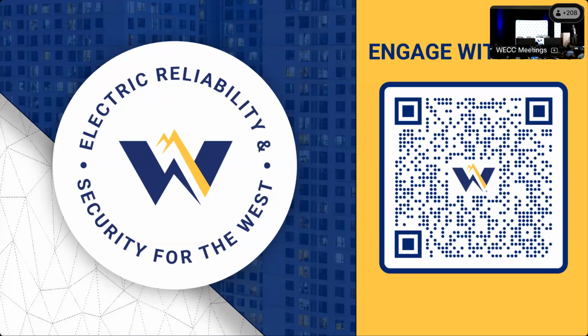It's kind of interesting. In the West, we maintain time error control. I don't know if anybody realizes that, but we do keep track of the frequency deviation over time. We call that time error. And we generally swing about plus or minus 200 seconds of time control in the West. Why that's important is clocks used to run on it. And if you've got a microwave and it's never in time, it's because we're swinging our system frequency that much on a yearly basis. So you can set your microwave today, and in 2 months it's going to be off again, and you're going to say, my microwave's gone bad. No, the frequency is consistently moving that much.